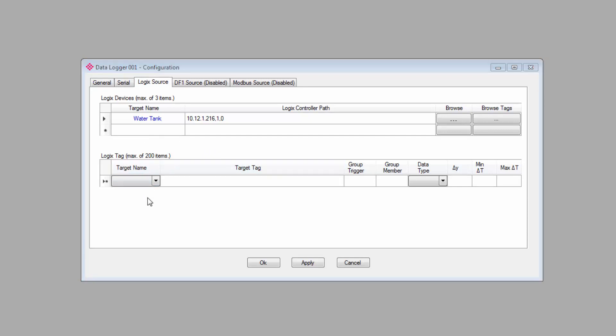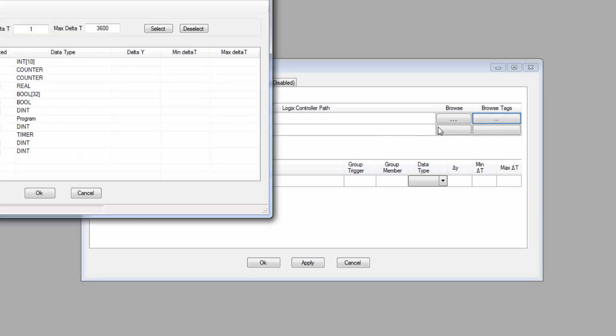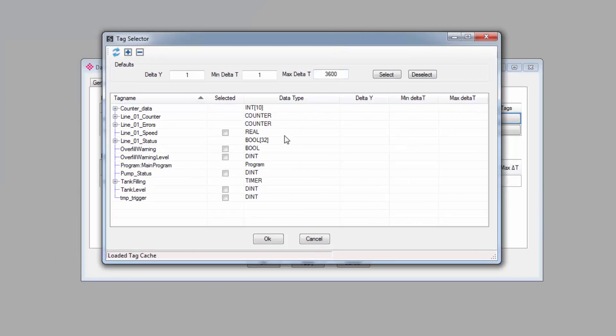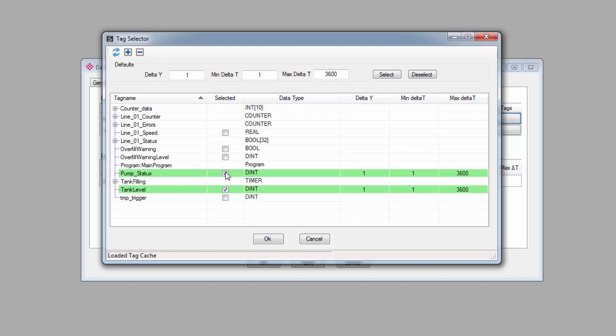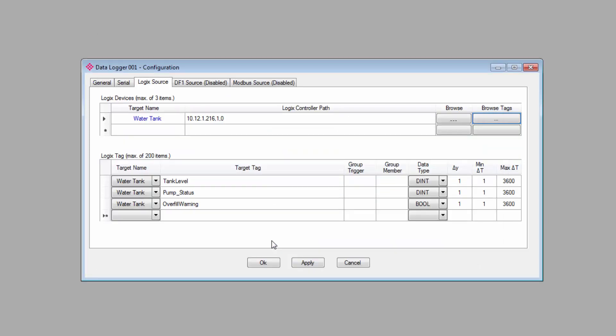At the bottom, under Logix tag, you can specify the data files in the controller that you want to log into the PLX51 database. To do this, you just click the Browse Tags button for the controller from which you want to log data, and the Tag Selector window will open up showing you the tags available from that controller. From here, you simply go through the list and check the box for each tag that you want to log. Once you have everything you want selected, click OK. The window will close, and all of those selected tags will appear in the target tag list below.